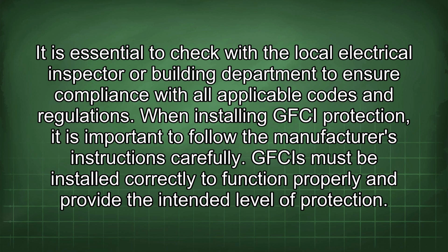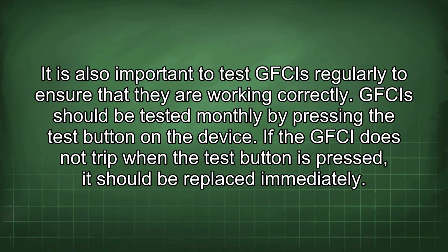When installing GFCI protection, it is important to follow the manufacturer's instructions carefully. GFCIs must be installed correctly to function properly and provide the intended level of protection. It is also important to test GFCIs regularly to ensure that they are working correctly. GFCIs should be tested monthly by pressing the test button on the device. If the GFCI does not trip when the test button is pressed, it should be replaced immediately.